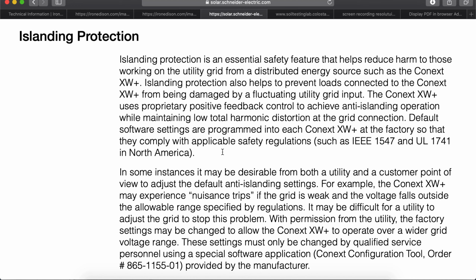Islanding protection. Islanding protection is an essential safety feature that helps reduce harm to those working on the utility grid from a distributed energy source, such as the Conext XW Plus inverter. Islanding protection also helps to prevent loads connected to the Conext XW Plus inverter from being damaged by a fluctuating utility grid input. I've seen this. The Conext XW Plus uses proprietary positive feedback control to achieve anti-islanding operation while maintaining low total harmonic distortion at the grid connection. Default software settings are programmed into each Conext XW Plus inverter at the Schneider Electric factory so that they comply with applicable safety regulations such as IEEE 1547 and UL 1741 in North America.